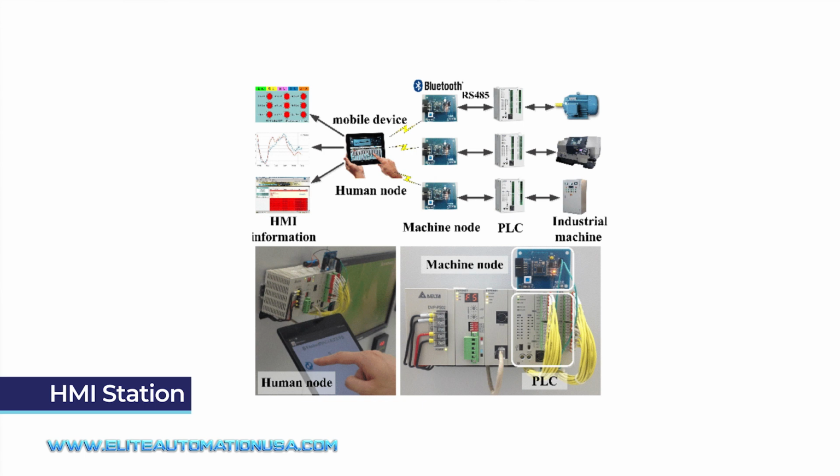Also, with the way these networks are being set up now, you can identify that the e-stop stopped working before anybody pressed it, right? You can send pulsed signals through the e-stop that continuously test, throughout its entire lifetime, whether the e-stop is good. So there's not any condition of Billy Joe hit that e-stop button and it didn't do anything. At least from a wiring standpoint, it can't be defeated and the wiring can't be manipulated. Everything is in a much safer condition.